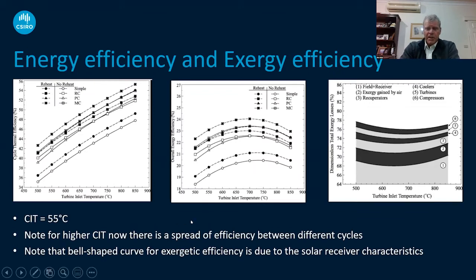Now, more realistically, in countries like Australia and Saudi Arabia, which have very high ambient temperatures, we're not going to be able to operate down around the critical point of 31 degrees C all that often. We're actually going to be operating at much higher compressor inlet temperatures. On the left here I show an efficiency curve for 55 degrees inlet temperature, quite a way away from the 31 degrees C critical temperature for CO2. What happens is there's a much greater spread of performance between those different cycles, especially the advanced cycles, and the advanced cycle is certainly coming into its own at these higher ambient temperatures.